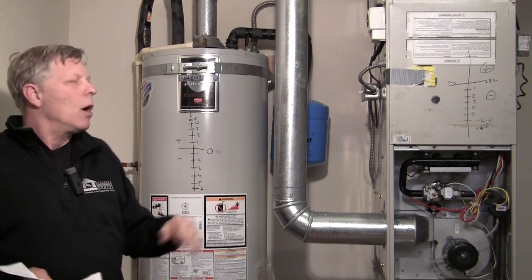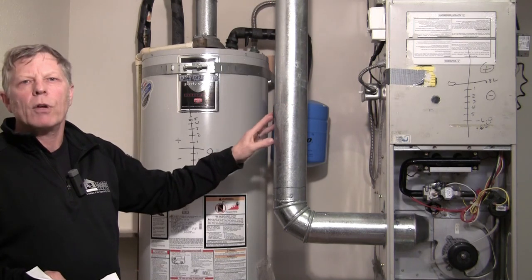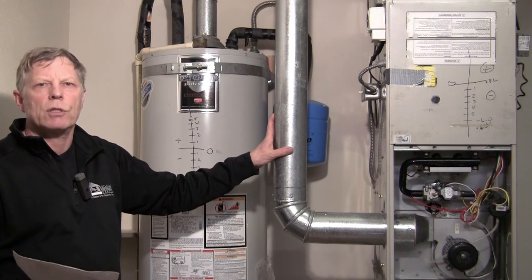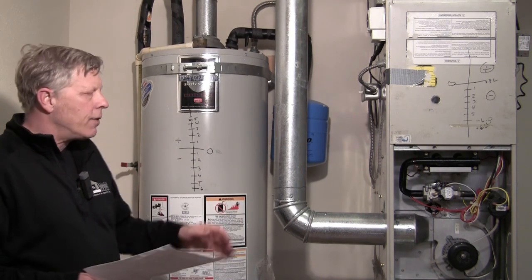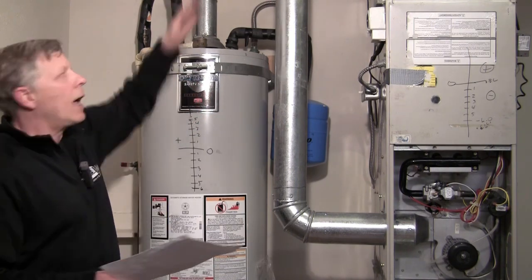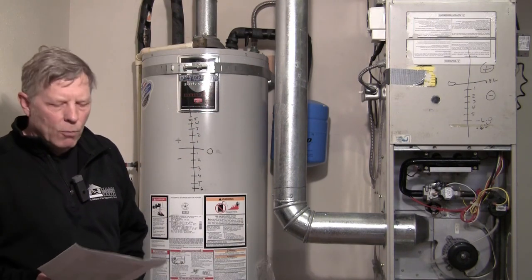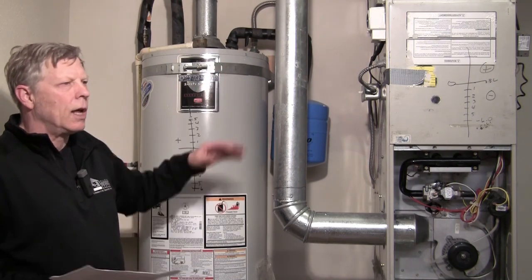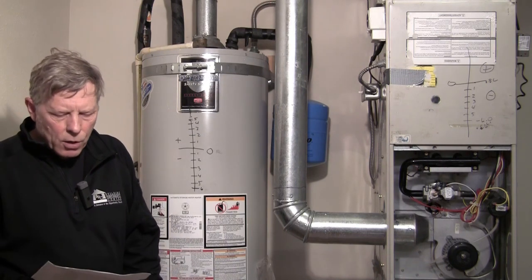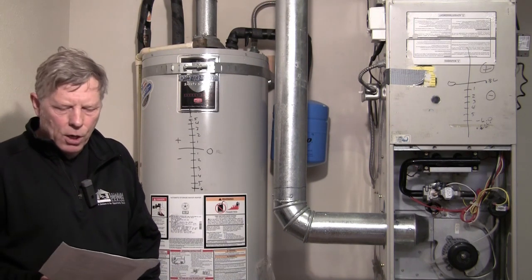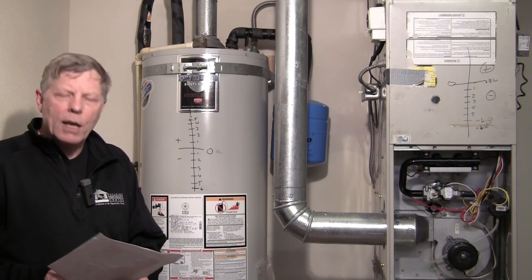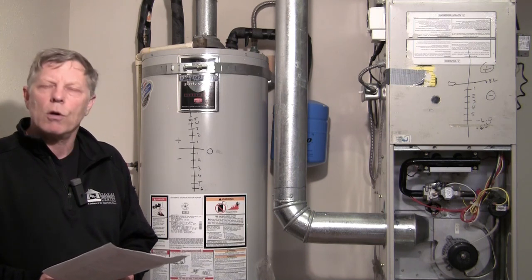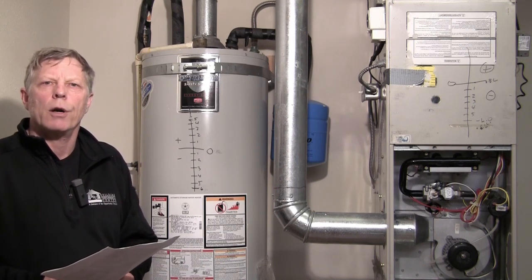And that's line 7. Well, since we're running the furnace here, we'll also get lines number 9 and 12 done, which is heat rise and efficiency, all right? If this water heater was standalone and it didn't have a shared chimney, then we'd use line 6. And if this furnace was standalone and it didn't have the water heater hooked to the chimney, we'd be using line 8. But for today, we're going to use line 7. So I'll go ahead and get it set back up in worst case, and we'll move ahead and do our CO and spillage assessment on this furnace and water heater.